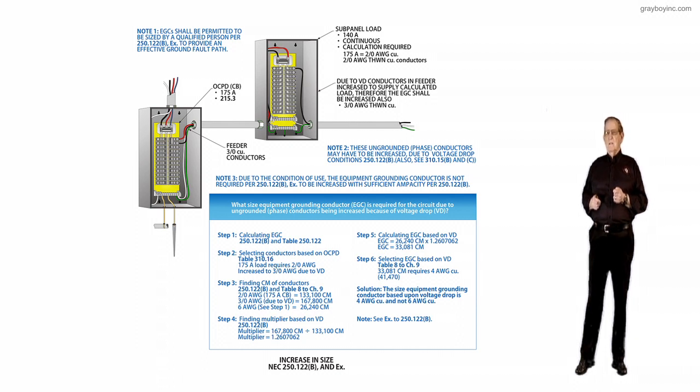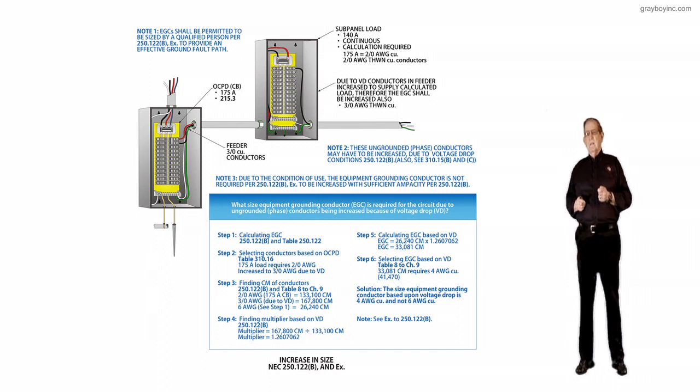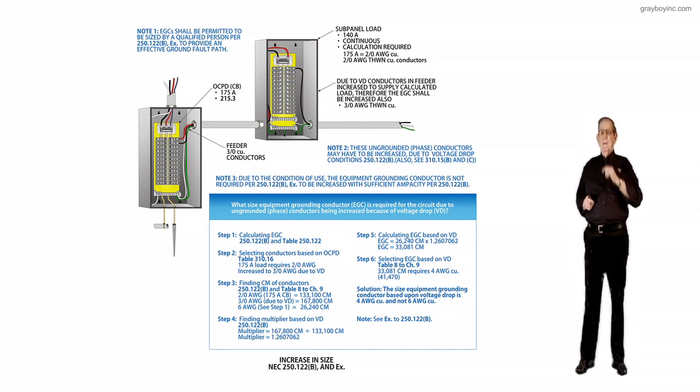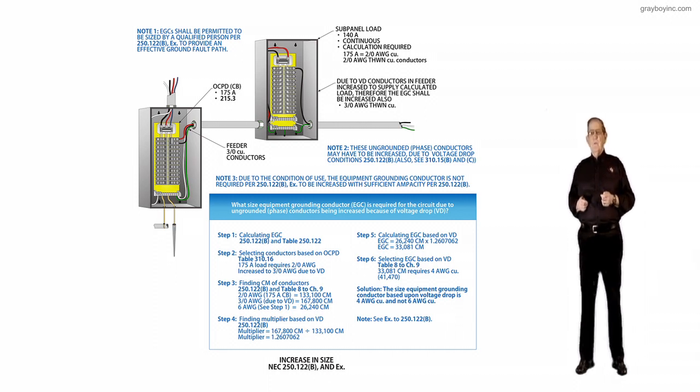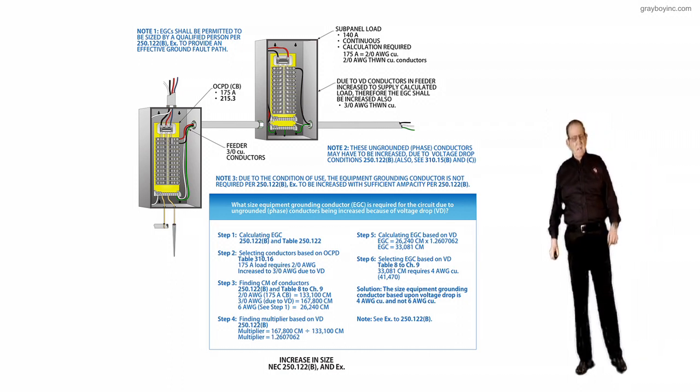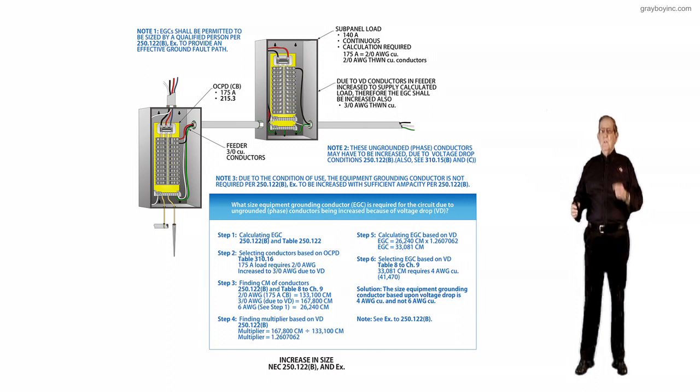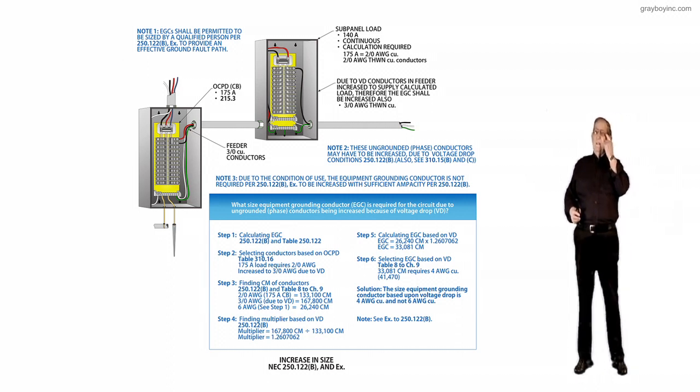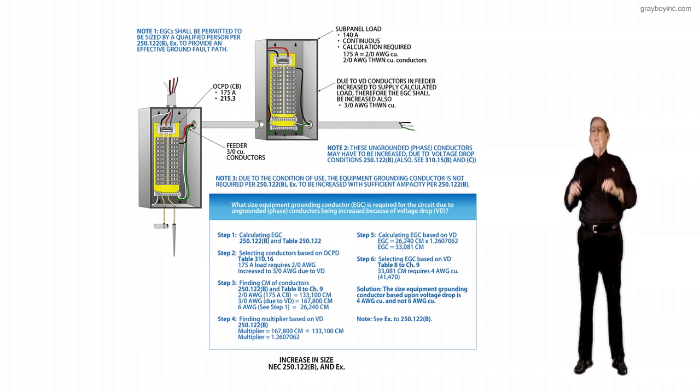250.4(B)(4). In other words, engineers wanted this back when we first upgraded and updated Article 250 and rewrote it. They said, look, we can prove that we have an effective ground fault path, but we can't prove necessarily that the system is effectively grounded throughout. So the engineers said, let's say effective ground fault path. And this is what they were kind of wanting to accomplish here.